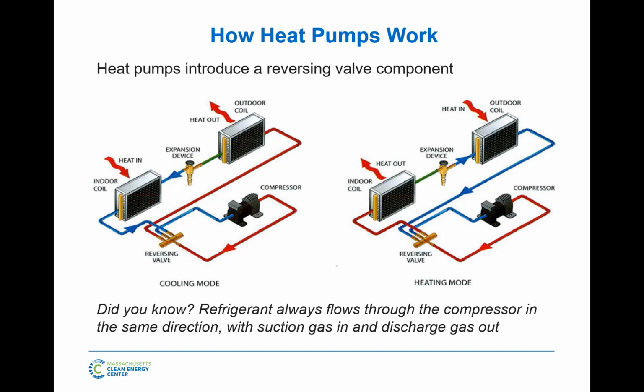Now, we don't just turn the flow the other way. Your flow is always going through a compressor in the same direction. We just add this component called the reversing valve. So in cooling mode in the summer, we send the discharge off the compressor to the condenser outside, so real hot gas can get cooled by the warmish air outside. Whereas in the winter, we take the discharge gas and send it right to the indoor unit, right to your coil, which is now technically a condenser. But we don't call them that. We call them fan coils, or indoor units, because again, they're condensers or evaporators. We just reverse the flow.